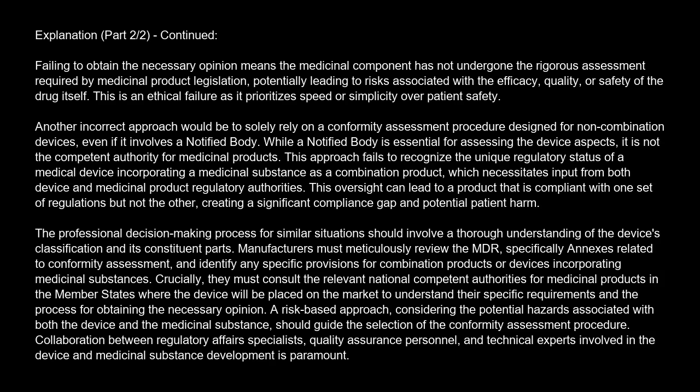Another incorrect approach would be to solely rely on a conformity assessment procedure designed for non-combination devices, even if it involves a notified body. While a notified body is essential for assessing the device aspects, it is not the competent authority for medicinal products.